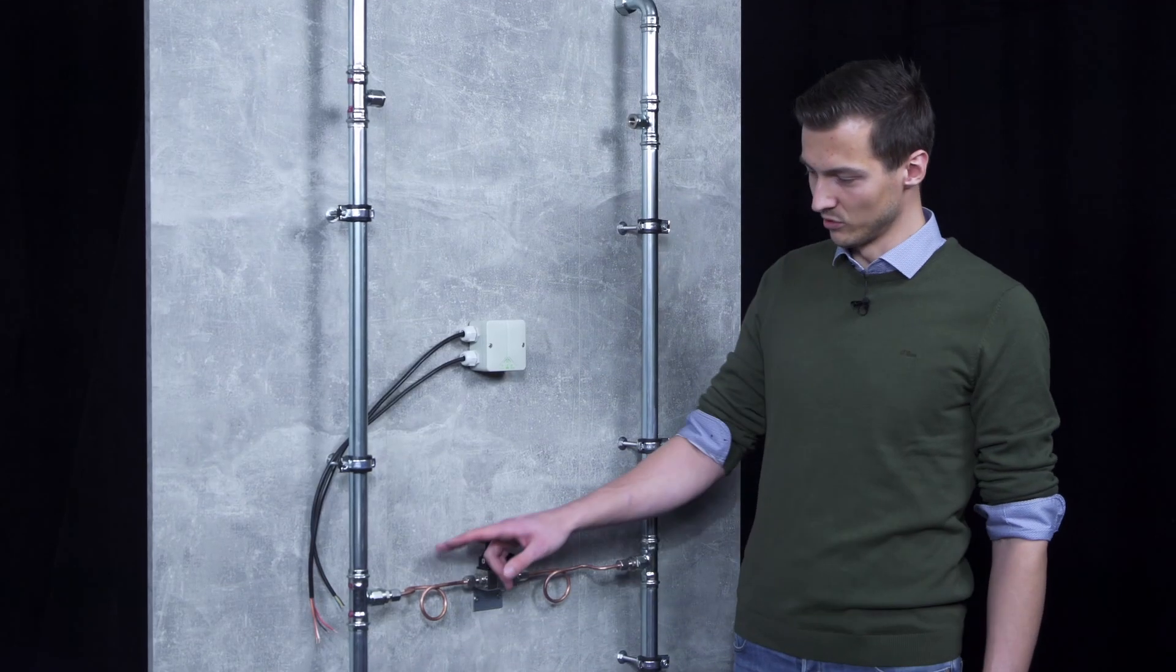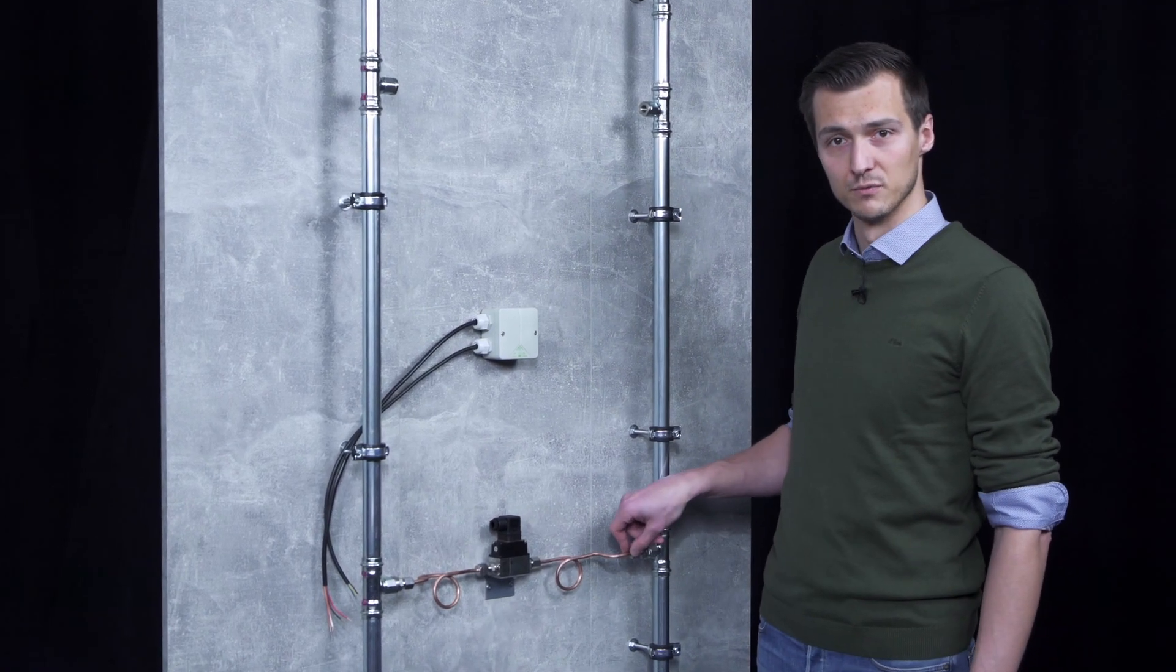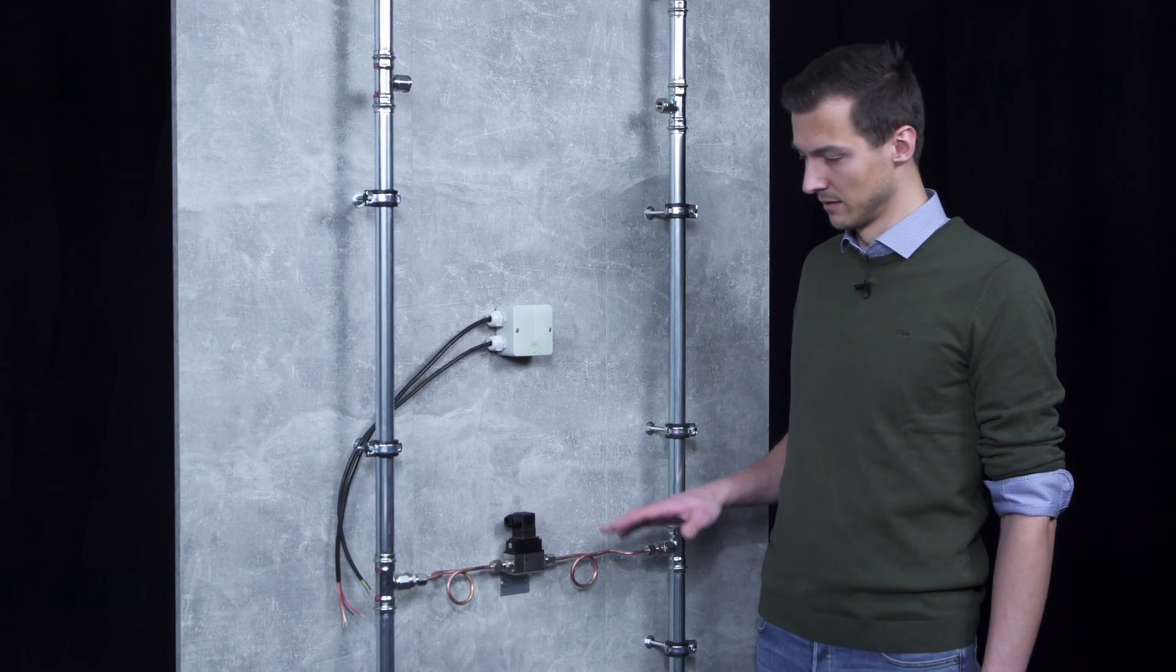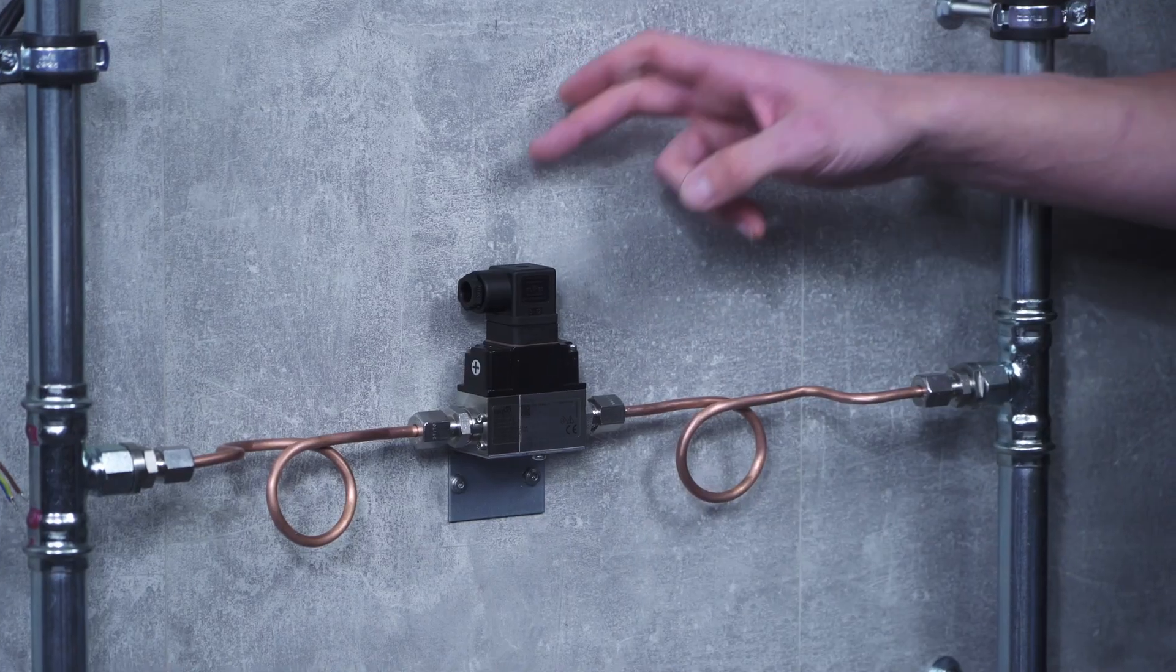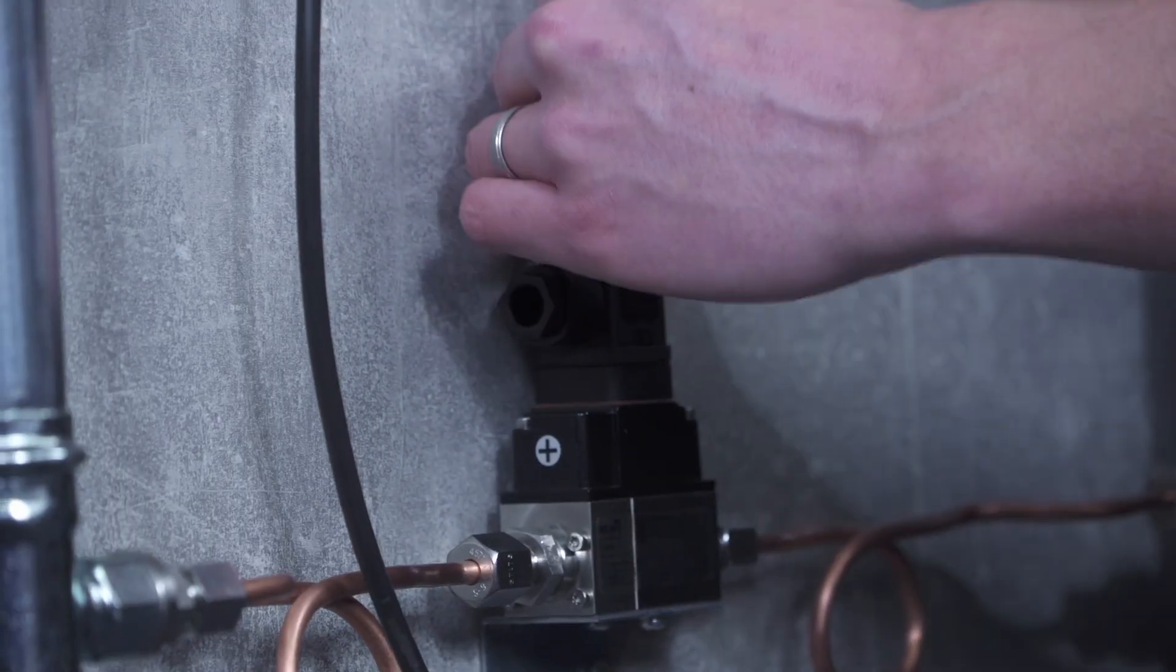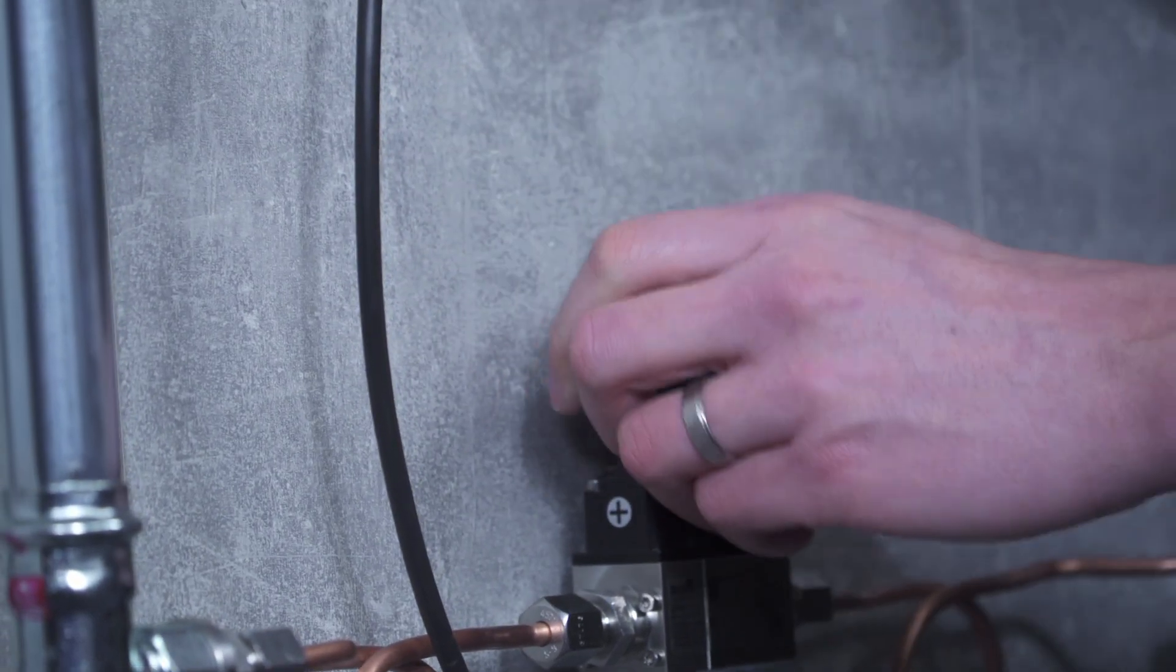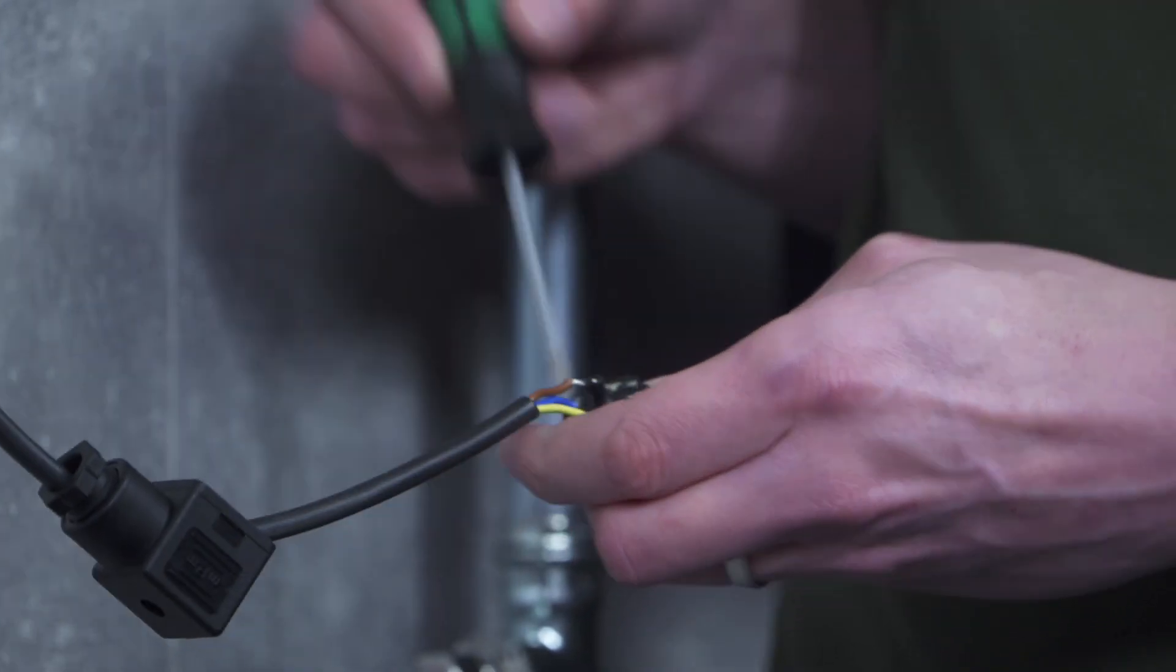I have now fitted both impulse lines, tightened the union nut so that the cutting ring seal, which completes the mechanical hydronic installation. We can now move to the electrical side. The connector plug is used for the connection. We first remove the plug and then route the cables to the plug accordingly.